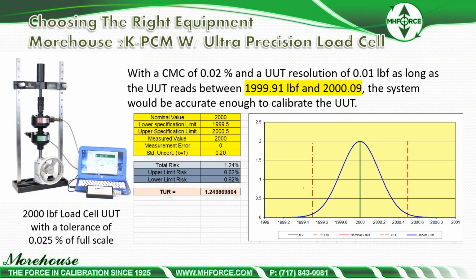And then if I want to have something like almost a 1-to-1 TUR, if I want to calibrate another load cell and I want this load cell to be better than 0.025% of full scale, I can do it.